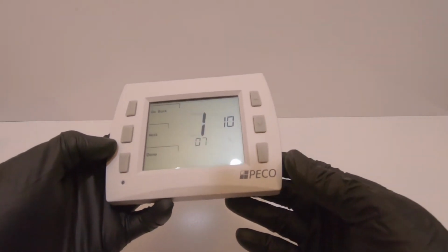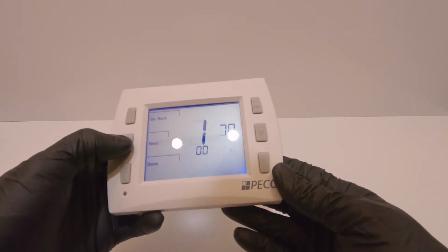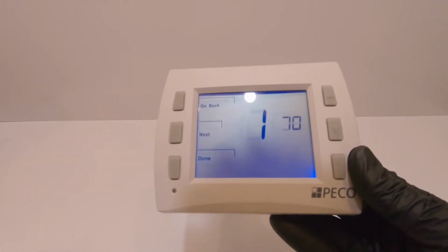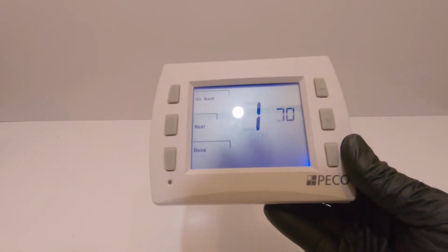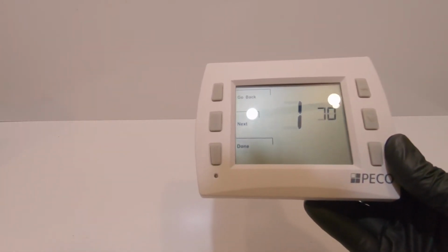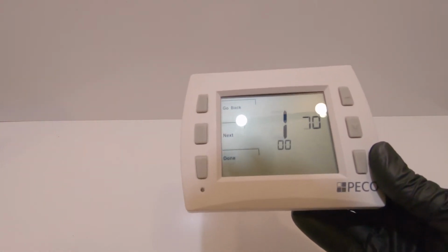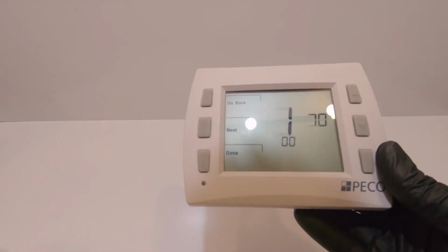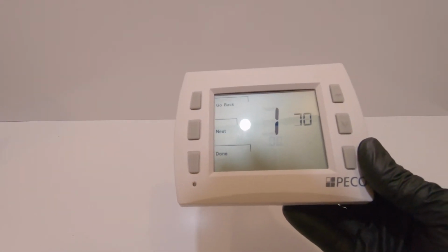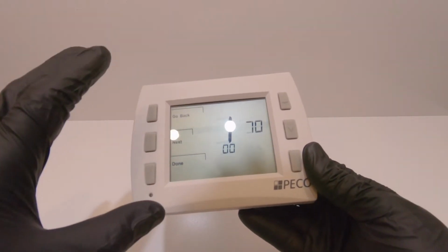And another one that I've noticed typically ends up being set up incorrectly is section 170. This has to do with the remote sensor. This particular setting is very important because if you have a remote sensor that is, let's say, out in the dining area and your thermostat is in the office, you want to make sure that it's going to be reading that remote sensor. Because if it's not, you're either going to have a situation where it's too warm or it's too cold.